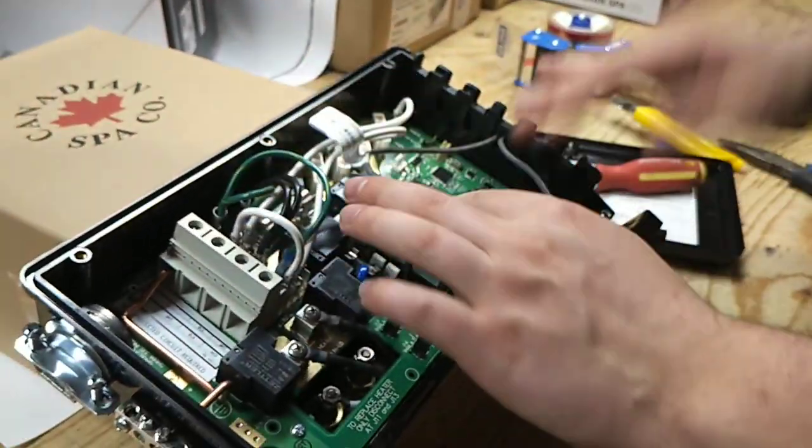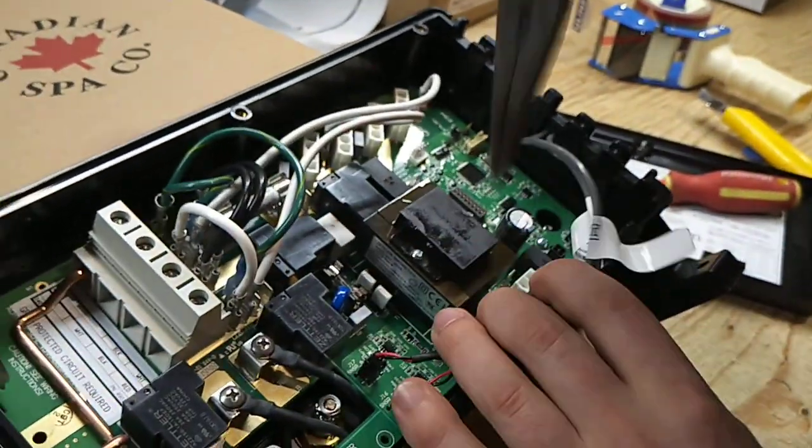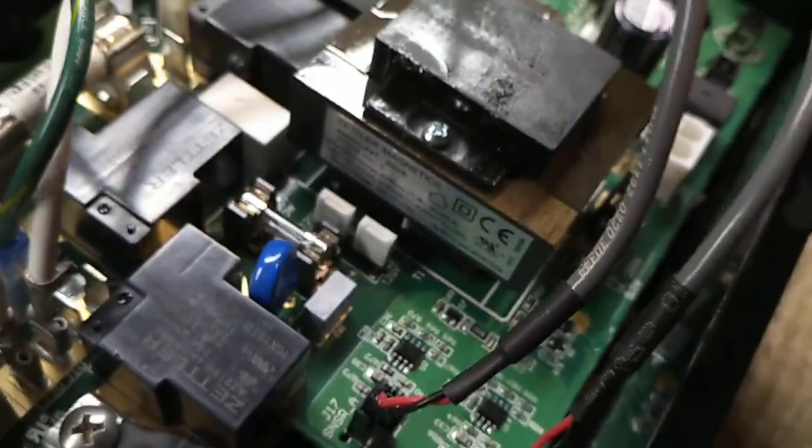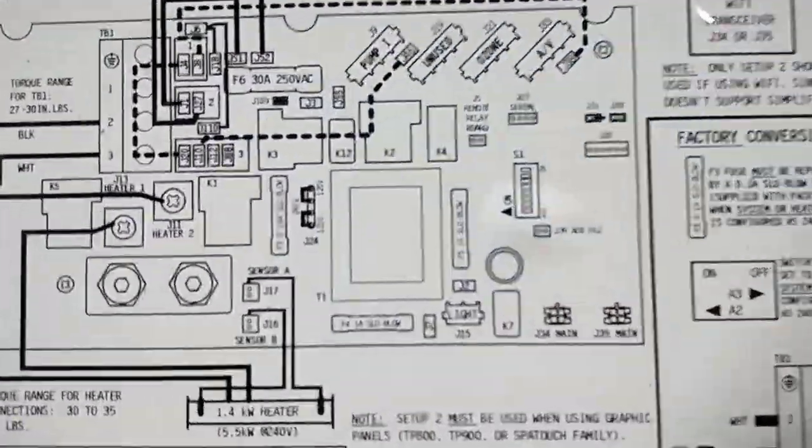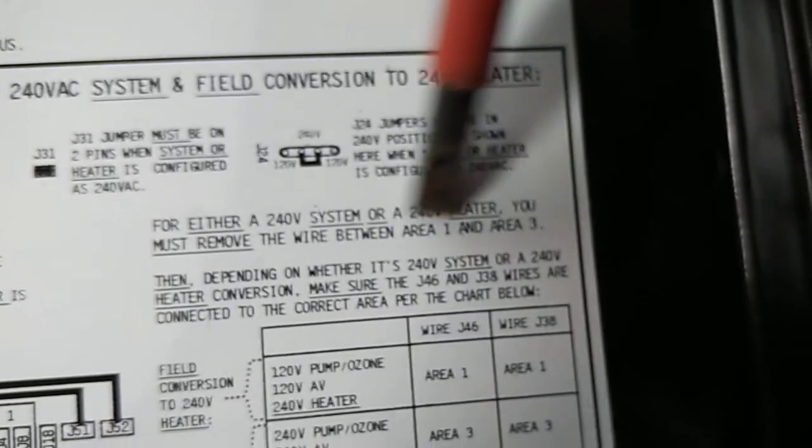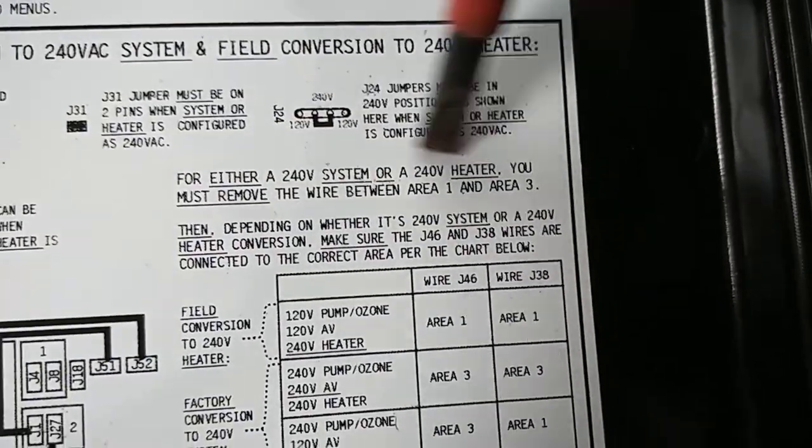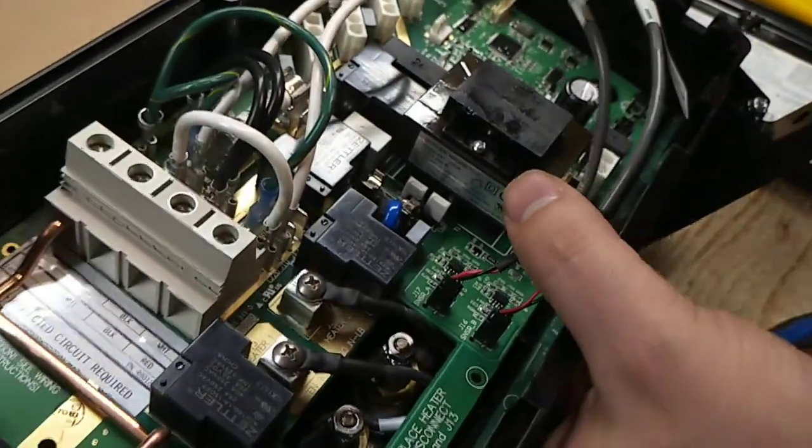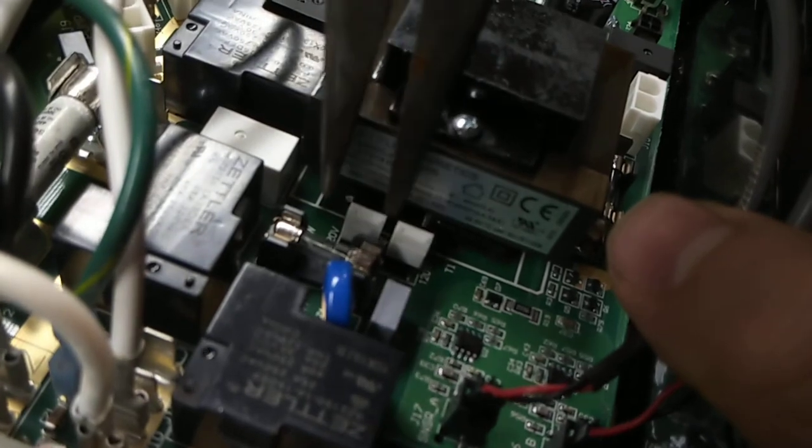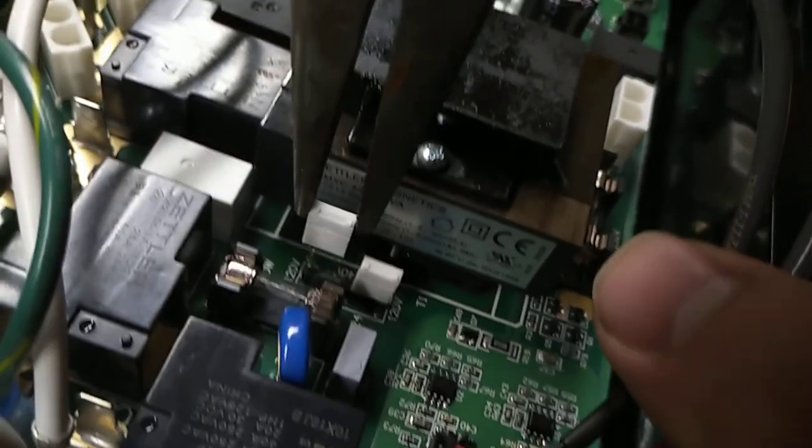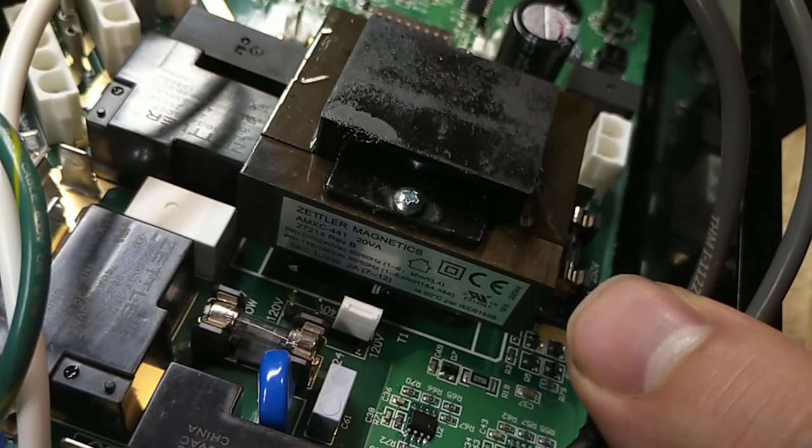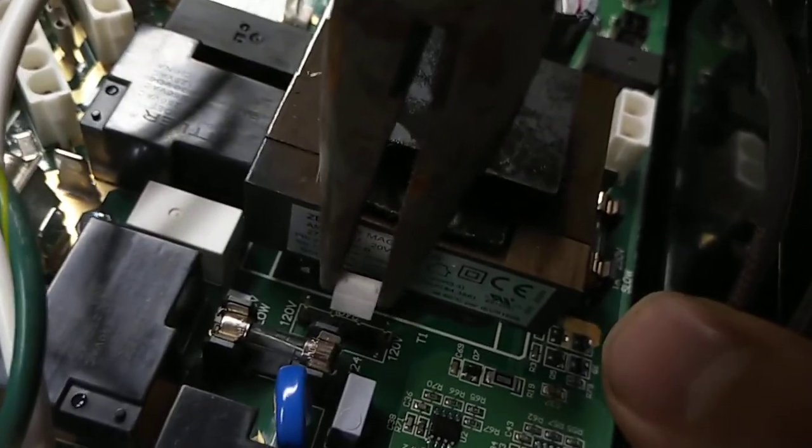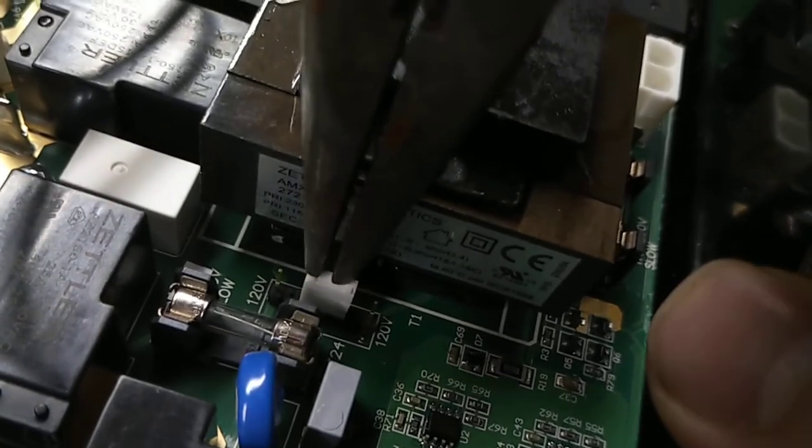Next step you want to look at is right beside it, these jumper pins here. This section, we're going to look on the wiring diagram. This is right here on the right over here. We're going to talk about what we're going to adjust right here with these jumper pins. So if you need to reference how to adjust that here. These jumper pins right now are set up for 120 volts because these white jumpers are located on the outside. So what we're going to do is actually take one off, grab it and put only one across the center two.